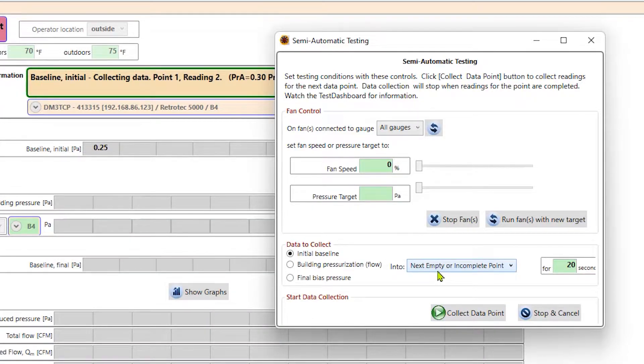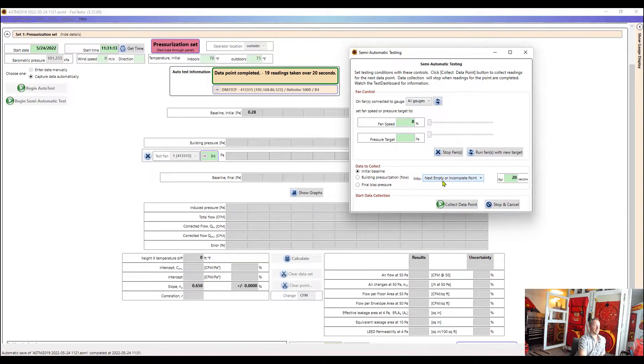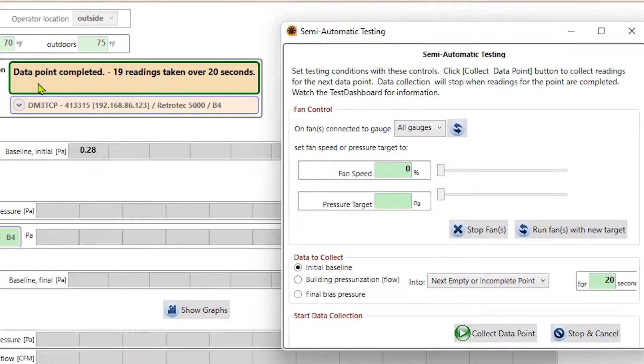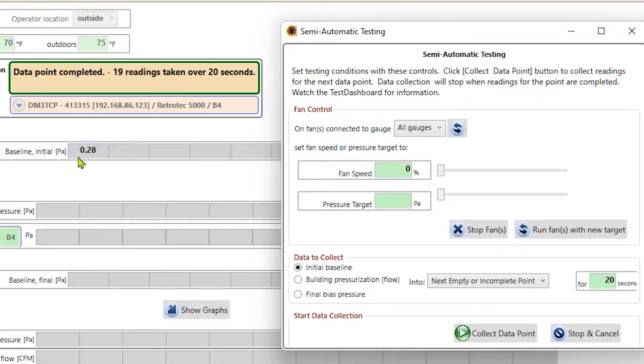Back in that settings menu, that's where I can change the amount of time that a baseline is collected. The default is 20 seconds. That's what a lot of standards call for. However, I can go in and change that. If it's a windier day and I want to collect longer baselines, then I can go into that settings menu and change that. Now I can see the data point is completed.